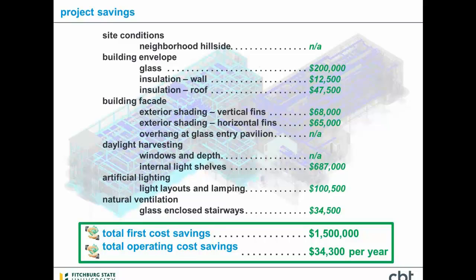Just for the things that we looked at alone, and this is independent of all the things the mechanical engineer was doing to create mechanical energy savings, we could easily have spent about $1.5 million on a variety of things that sound good, sound prudent, sound like energy-conscious and sustainable approaches, but when you actually boil them down and look at it, there's maybe a more effective way of addressing the exact same issue. In addition to the first cost savings, which you're then able to put directly back into the programming and benefit directly the people who are using the building, on top of the savings that the mechanical engineers were realizing, for these things we studied, the building performance itself was able to reduce the annual building energy consumption by almost $35,000, about $34,000 a year.